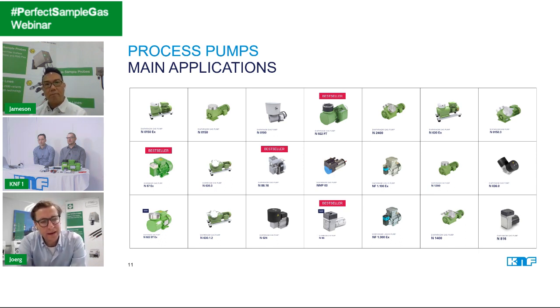But then you said this is regarding bringing the sample back to the process. You're right. Or sometimes even the analyzer needs more pressure. So sometimes we have a pre-pressure of 1 or 2 bar in the lines and suck the sample out with the pump, and maybe the analyzer needs 4, 5, or 6 bar. There are some analyzers on the market that need that pressure, and therefore you need to increase the pressure through the pump. And as Stefan mentioned, the second application is to bring the gas back into the process. These are the two main applications in the process area with the bigger pumps. Okay, I understand.